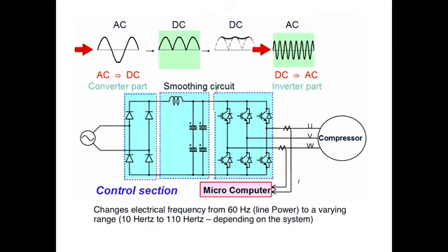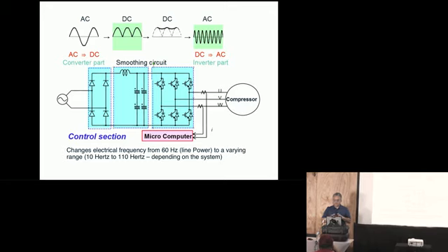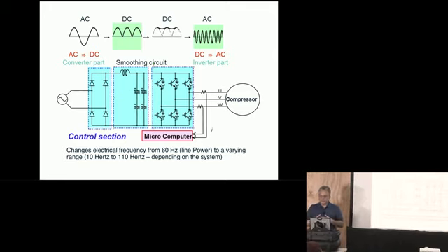Then it's converted from DC to AC. Once the voltage is controlled by the software, the voltage frequency, which in the US is 60 cycles per second or 60 hertz, can either be increased or decreased to suit the demand. So fun fact, nearly all, if not all, single zone ductless mini splits are three-phase compressors. Who knew that? Single zone, fun fact, all of them are typically three-phase compressors. So yeah, one of the lines is a simulated third leg.